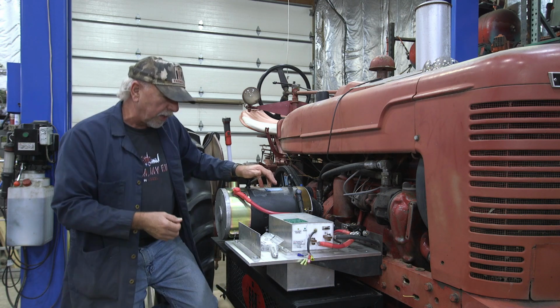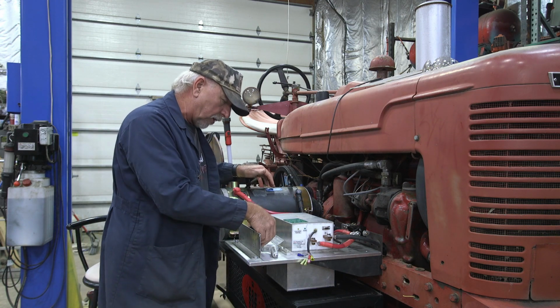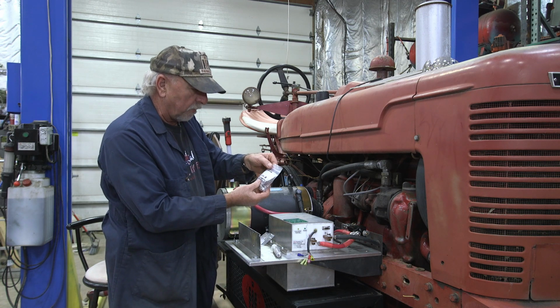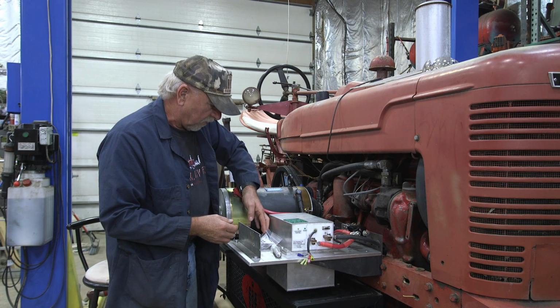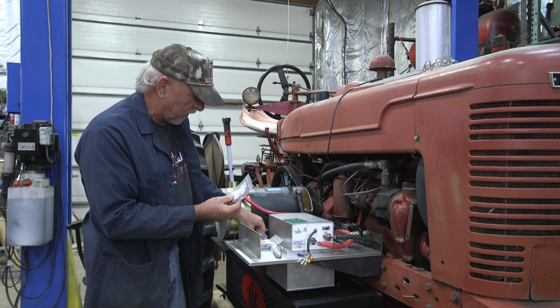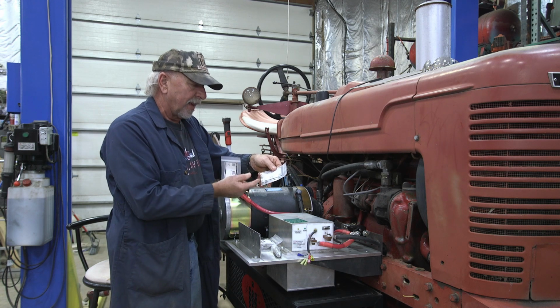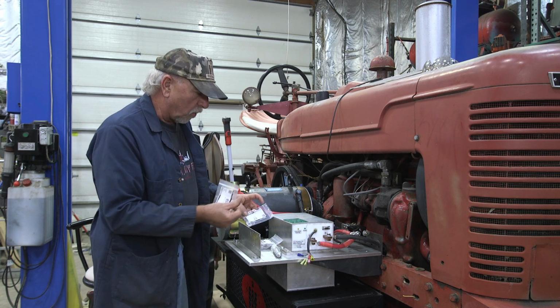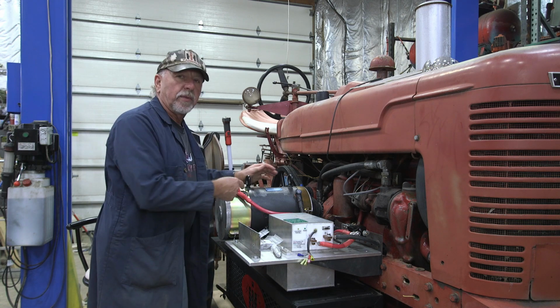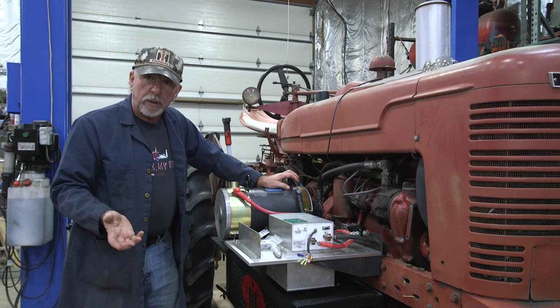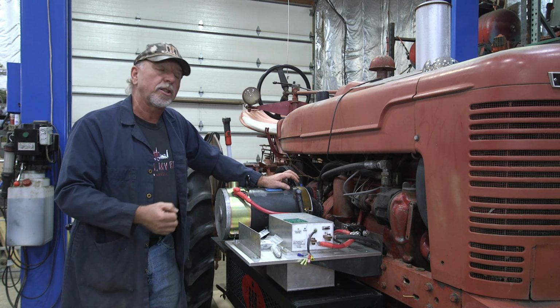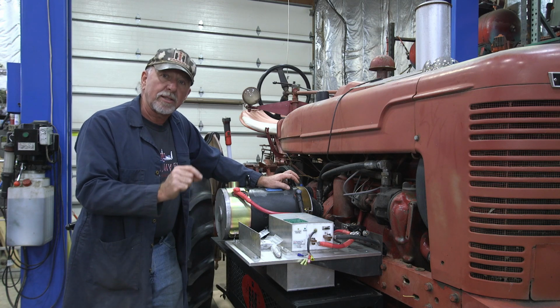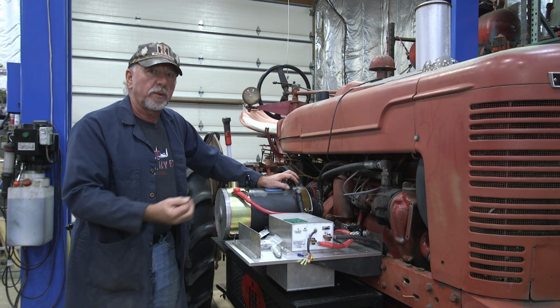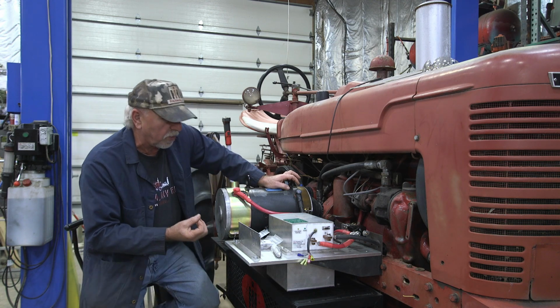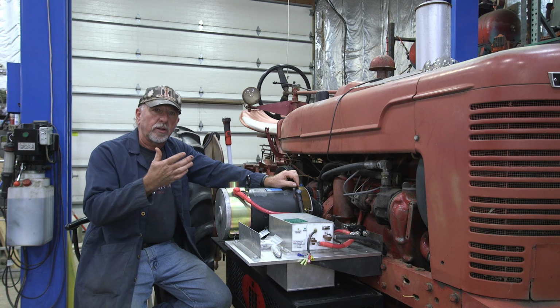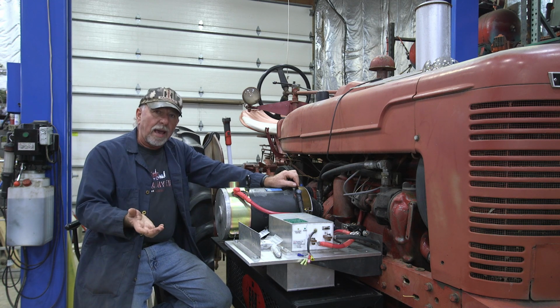Batteries all hooked up. The hardware I used at the termination points was a high quality stainless steel bolt, a bronze washer, and a high quality stainless steel star washer to get penetration on the surface area of the cable itself. Everything was torqued to specifications. I had looked up the specifications based on the bolt design and fastener type, so unlike the batteries, I had to come up with my own spec for that. That's something very critical that will be maintained, and the torque will be checked because of the heat and vibration.